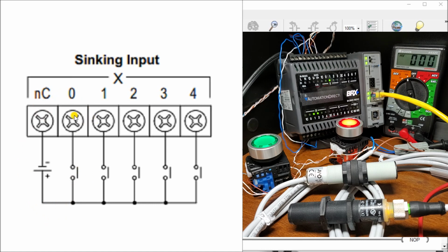And remember, we are measuring across our load to determine whether or not we have power or not power, 0 or 24 volt. This is an excellent way of troubleshooting and allowing you to determine if that input is still functional or if the actual sensor that we have to that input is functional.